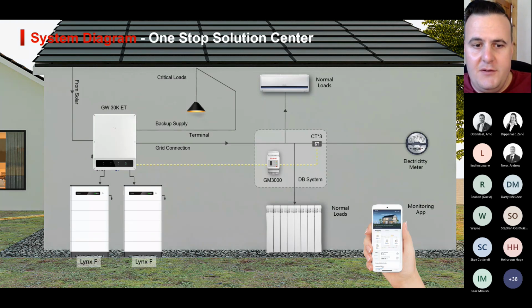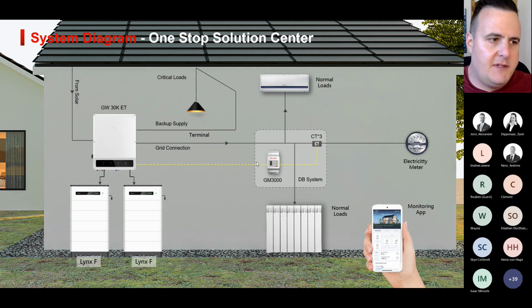Then next, we're looking at our new ET, so the 15 to 30 kilowatt ET series. Here's an overview of the ET series. We'll look at the data sheets a little bit later. So this is a 30 kilowatt. The 25 and the 30 kilowatt both have dual battery inputs, so you can have two different battery banks on the inverter itself. And they do come supplied with a GM3000 smart meter. The new smart meter comes with 200 amp CTs, where the old ones were only 120 amp.